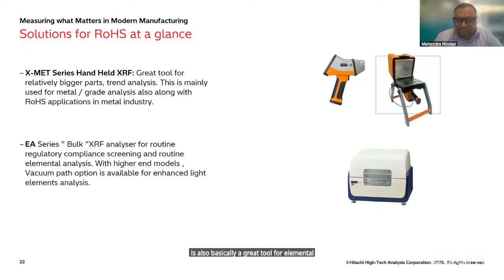But generally, if the samples are small and you need a really accurate analysis, we recommend going with a benchtop XRF. Also, a benchtop XRF can do elemental analysis. So not only RoHS, you can do other elemental analysis also. XRF is a great tool for elemental analysis. XRF comes with metal calibration, plastic calibration, and solder calibration. These are the typical things industry wants to check for RoHS compliance. A handheld XRF is generally suitable for pure solder metal, but if it is on the PCB, it's very difficult to hold it in the hand and check it on the PCB. These things you can do only on a benchtop XRF.